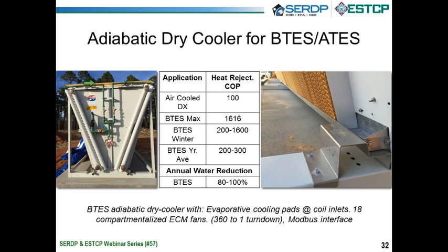At Fort Benning, a smaller 35-ton system, these adiabatic dry coolers have about six fans on there, and the pads, if you come over here, if you're from Georgia, you see these all over the place. They're on the inlet side of a chicken house. In a chicken house, in most places, you can't afford the chicken if they air condition them. So we evaporate water through these pads, so-called swamp cooling sometimes, evaporative cooling, or if you're a geek, adiabatic cooling. We cool that outside air adiabatically, and the air is pretty saturated, but it's not wet. And then the air, after passing through the evaporative pad, strikes the coil and is carried up and out. So that's an adiabatic dry cooler.